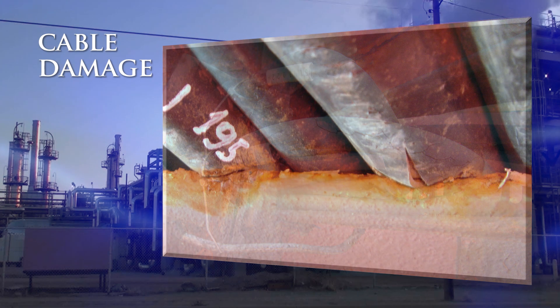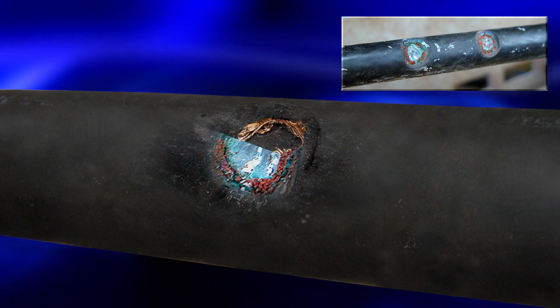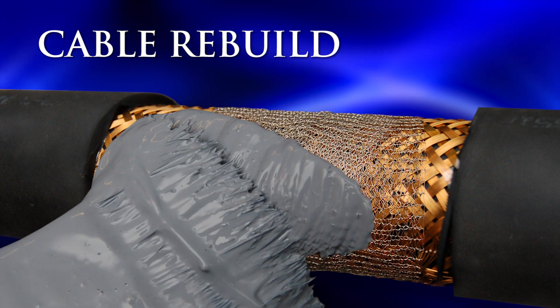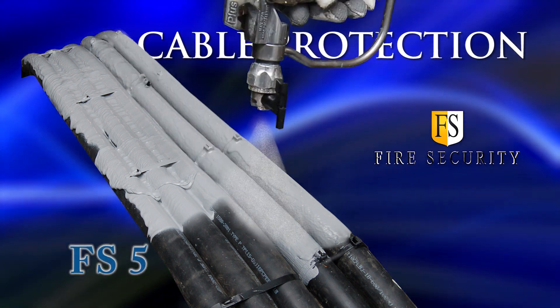Rerouting or replacing damaged cables may involve extended shutdown periods. If the outer sheath and the cable screen are damaged, we rebuild the screen by use of a metal shielding tape and use a fiber mesh to gain mechanical strength. The excellent properties of the FS5 coating ensure that the insulation property is completely rebuilt. The cables are upgraded to the highest level of fire safety and the operational life is radically extended.